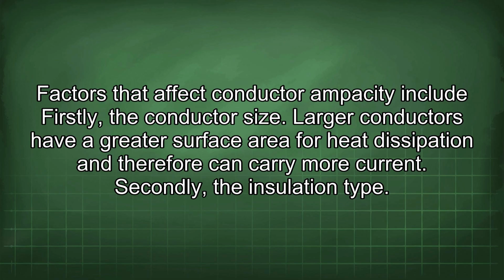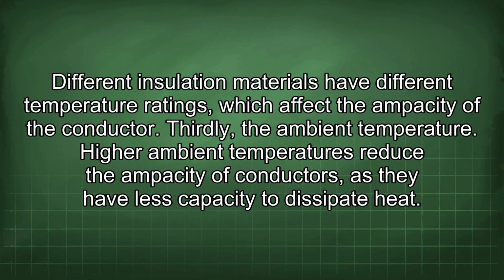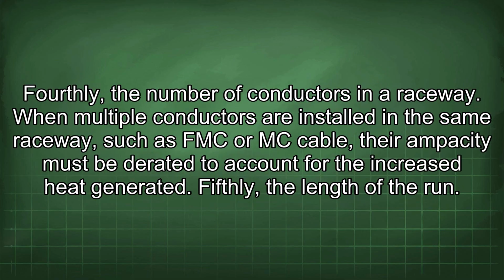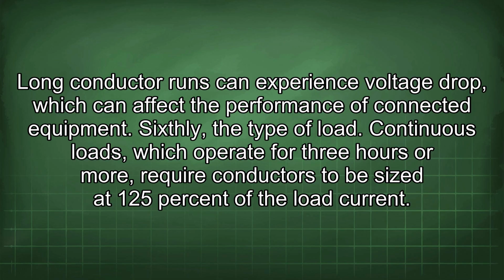Factors that affect conductor ampacity include, firstly, the conductor size. Larger conductors have a greater surface area for heat dissipation and therefore can carry more current. Secondly, the insulation type. Different insulation materials have different temperature ratings, which affect the ampacity of the conductor. Thirdly, the ambient temperature. Higher ambient temperatures reduce the ampacity of conductors, as they have less capacity to dissipate heat. Fourthly, the number of conductors in a raceway. When multiple conductors are installed in the same raceway, such as FMC or MC cable, their ampacity must be derated to account for the increased heat generated. Fifthly, the length of the run. Long conductor runs can experience voltage drop, which can affect the performance of connected equipment.